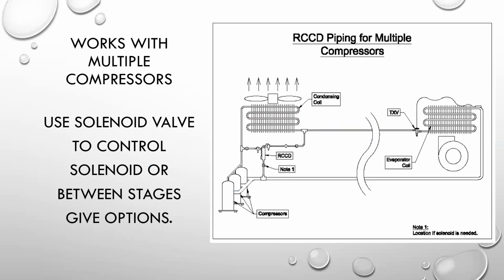It can go on multiple compressors, and a lot of times you'll see note number 1. It says location if solenoid is needed. There are instances where you may have a 40-ton package with 4 10-ton compressors, and your issue isn't with the bottom side, it's between the stages. You put the valve in, and then you activate that solenoid when the second stage comes on. And what that does is, yes, 10 tons is 25%, but now you've got modulation of the 7 tons between stages, which helps out with humidity control and also keeps you from short cycling the compressors in between stages.